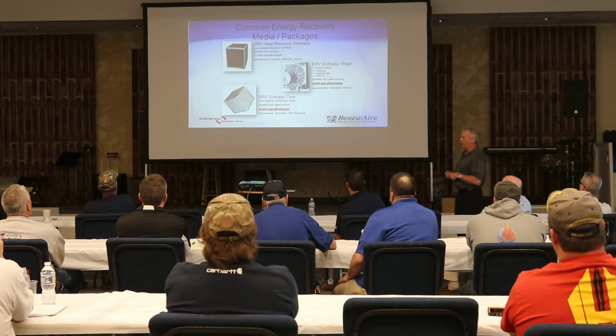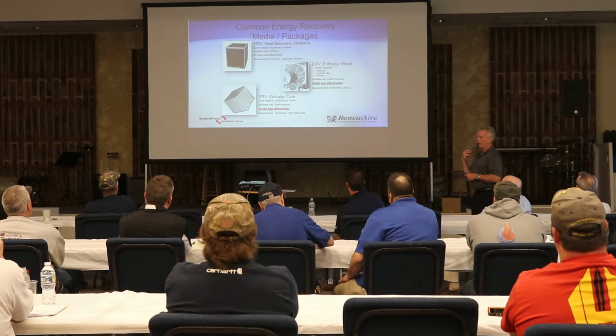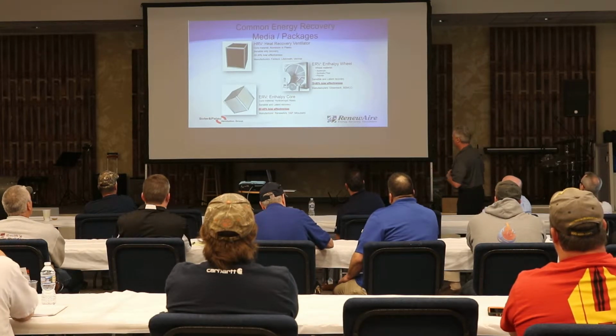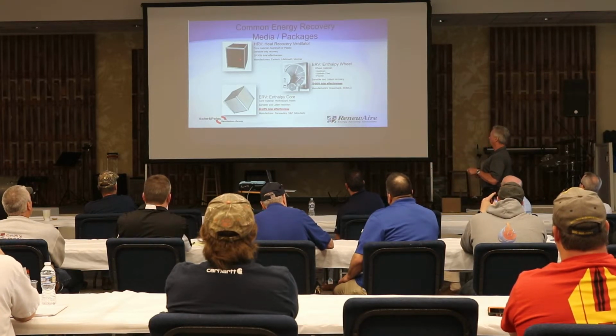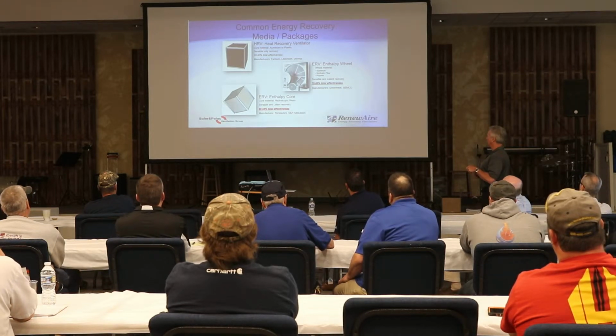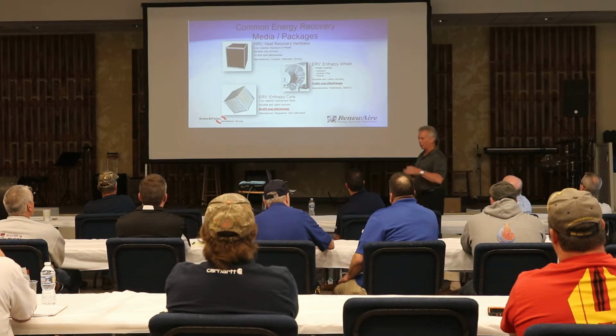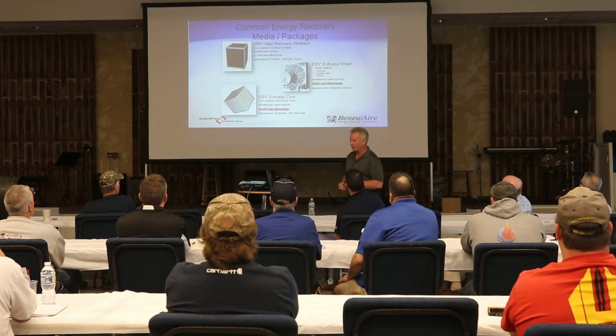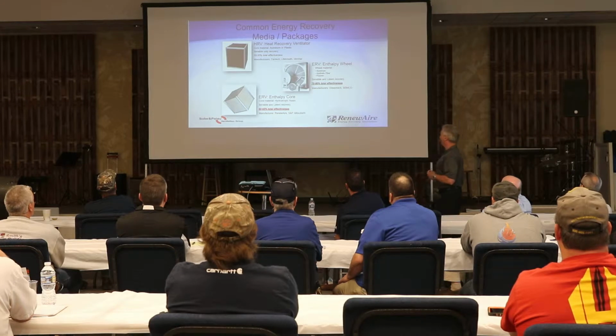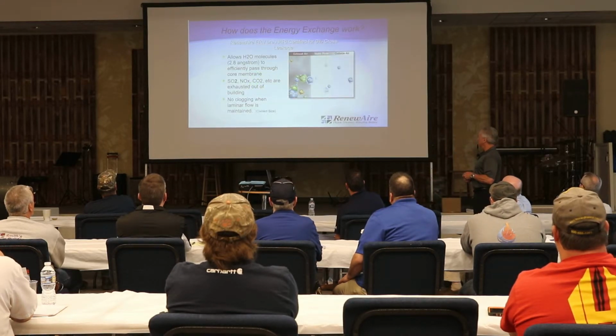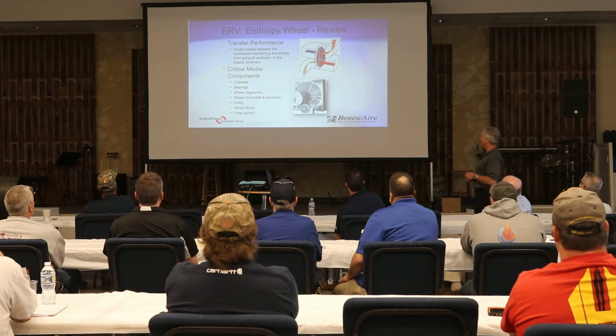These are some of the common media or heat exchange packages that are available. Heat recovery ventilators are pretty much going to come in one flavor, if you will. It's a static plate core made of aluminum or plastic. It is sensible only in recovery. In other words, sensible heat, that heat which you can feel, something other than latent. The total effectiveness, I've given away the show.